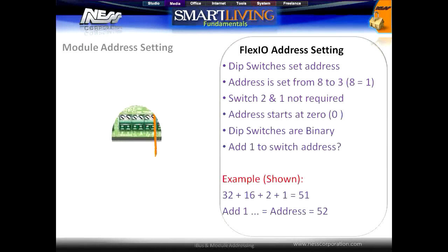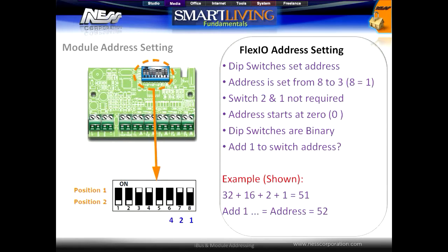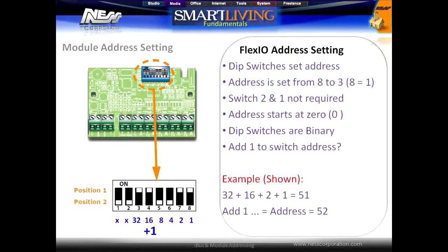The FlexIO module is addressed using the onboard DIP switches, using switches 8 to 3, with switches 1 and 2 not being used. As depicted by the diagram, each switch corresponds to a binary digit, and combinations of these switches add up to the address. It should be noted that with all switches off, a value of 0 equals module number 1, meaning that for any value you need to add 1 to get the module's address.